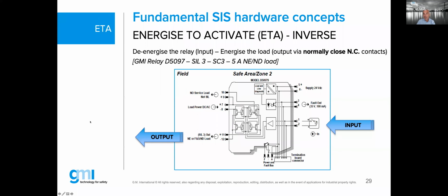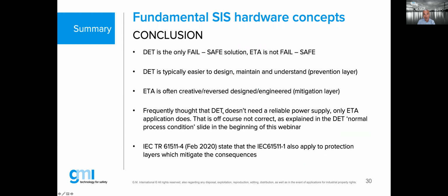Energize to activate. So what I'm trying to say is, often we will mix those. Let's say the majority of your safety PLC signals, your outputs, are all de-energized to trip, and you have a few energized to activate loops that you still want to mix in the same platform. You may keep your logic in the same zero logic, we call this, and you may reverse this output with this type of relay, which we show over here.